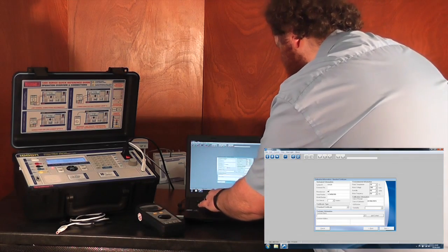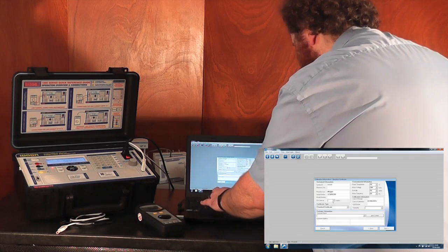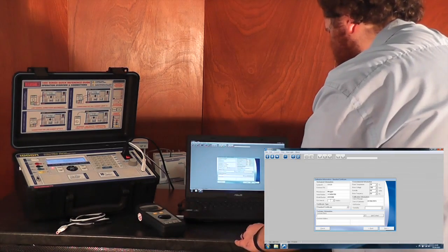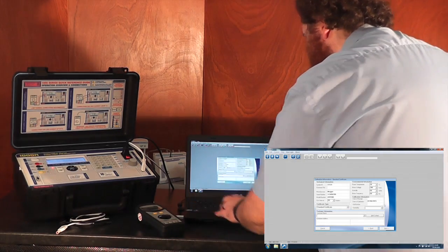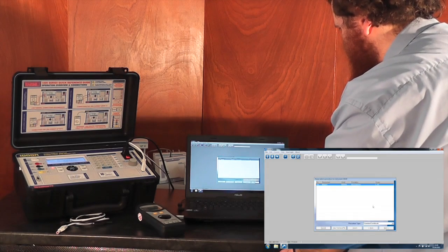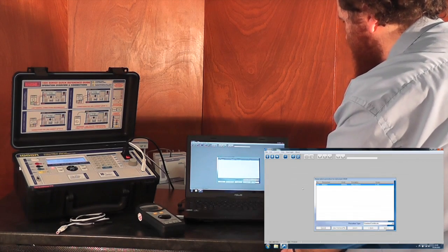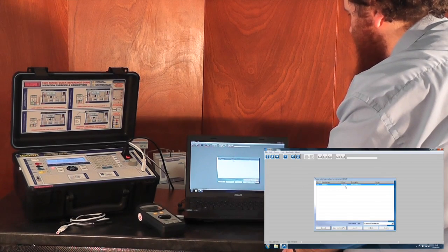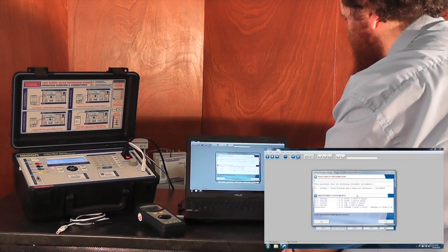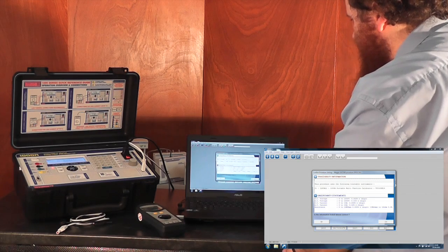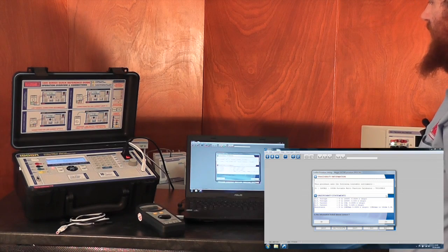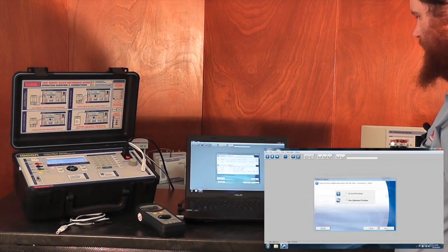enter the manufacturer, the model number, as well as enter the desired calibration interval. ProCal has automatically selected the correct procedure from the manufacturer and the model number we have just entered. It's listing here the traceability information, showing that we're using the 1000 series we configured earlier.